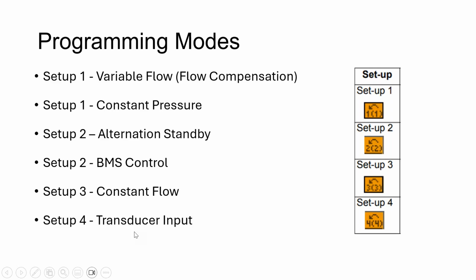I do want to make sure I challenge you folks to think outside the box a little bit. Again, right? That's the 10th time I've said that this presentation. If you ever are going to get involved in specifying a self-sensing pump, make sure the whole team understands that, because we have had situations where not everybody realized on the project that they didn't need the transducer mounted in the wiring. And so all of a sudden at the end of the project, hey, where do I wire this? Wire it in, and they're planning to use it because maybe the control guy or whatnot didn't communicate. So just keep that in mind.